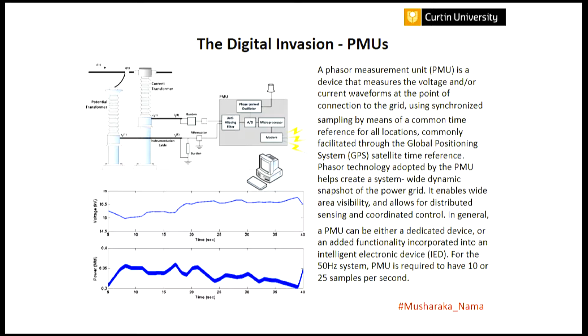For example, you could dynamically manage the power flowing through an electricity transmission system. When a transmission line is designed, it's designed for a particular wind speed and temperature, but actual conditions vary. Depending on line sag, operating conditions, and load, you can dynamically rate your transmission lines. Using phasor measurement units, you can determine in real time the actual capability of a transmission line, which can help avoid congestion problems in the transmission network.